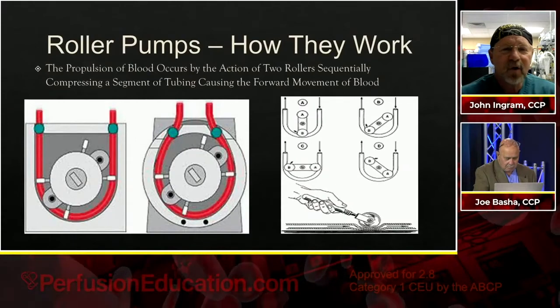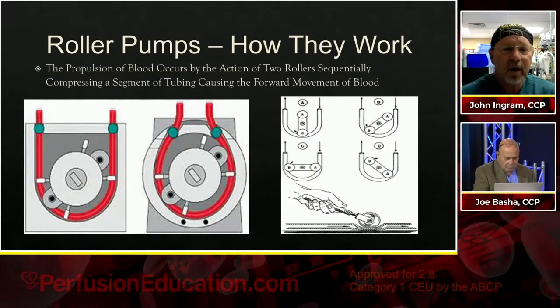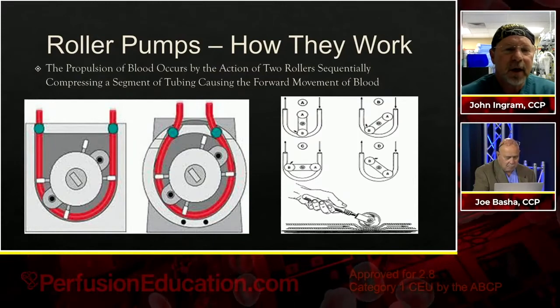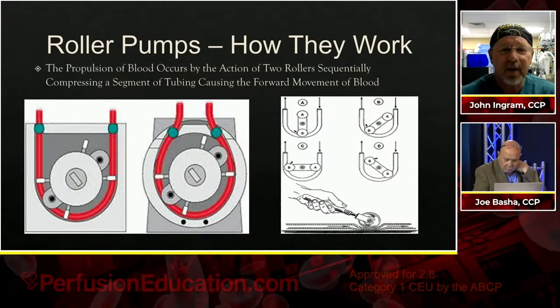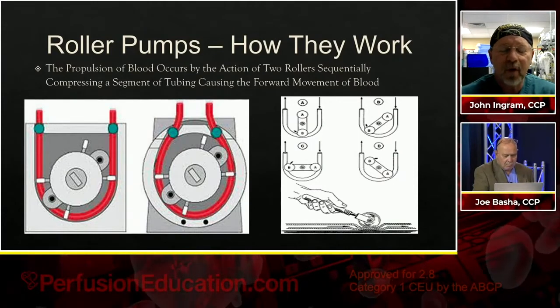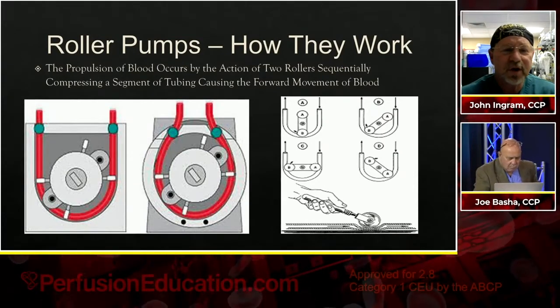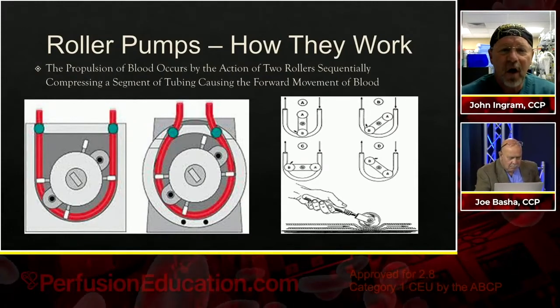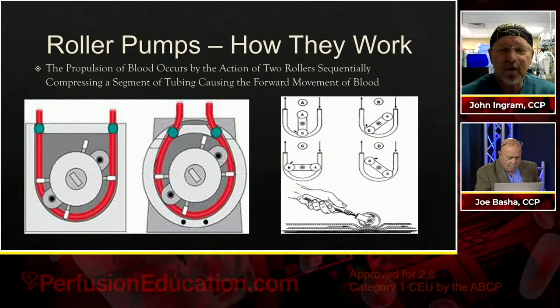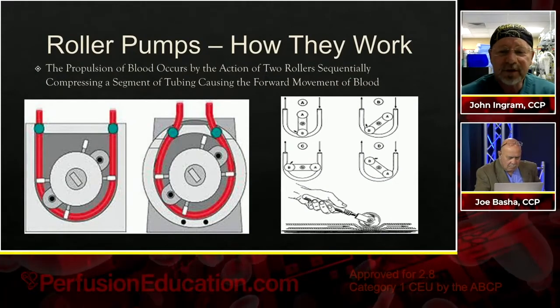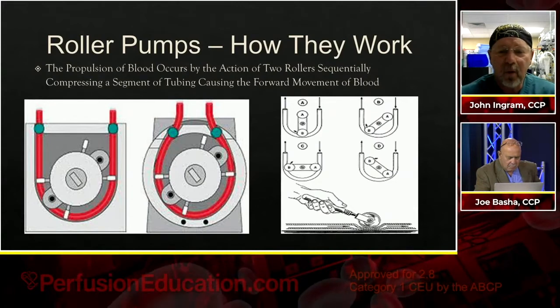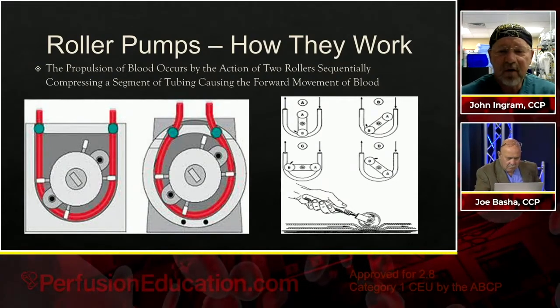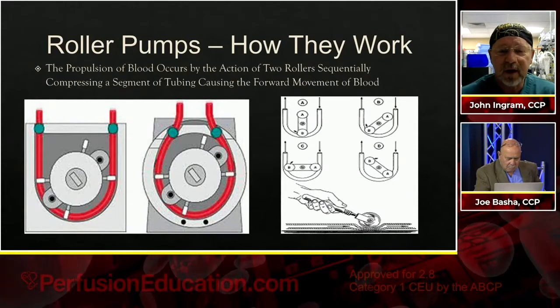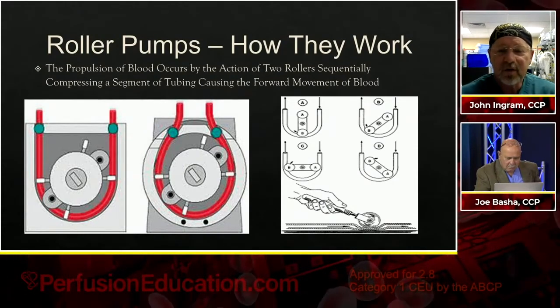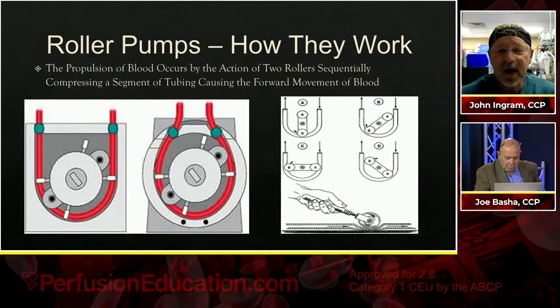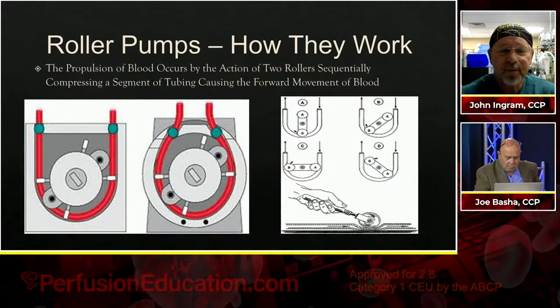Go ahead, Jim. All right, so let's look at roller pumps, how they work. I've got two graphics there, but basically it's a propulsion of blood that occurs by the action of two, or sometimes more, but in most perfusion cases two rollers sequentially compressing a segment of tubing, causing the forward movement of blood. If you look at the right-hand graph, at the very lower part of that one, it shows that if you were to take a tubing full of fluid and run a roller over it, compressing it almost all the way down, of course the fluid would move forward. And this is exactly what we're doing with the roller pumps that we use today.